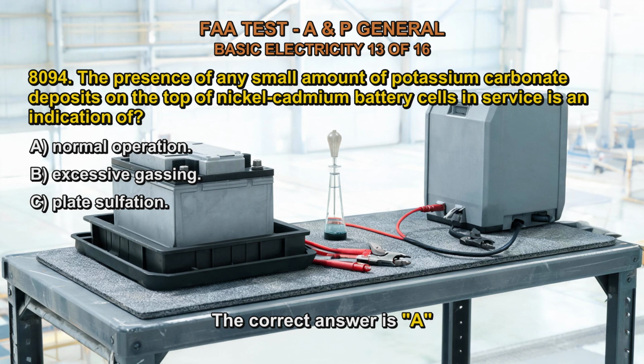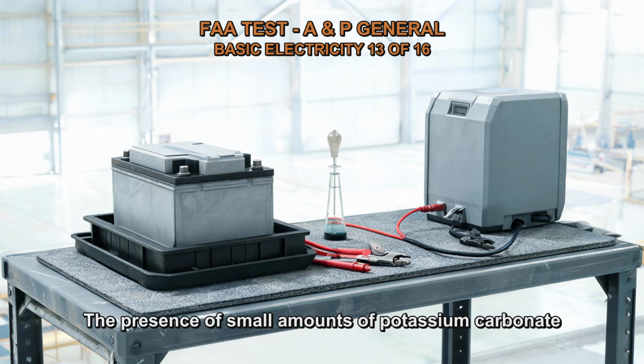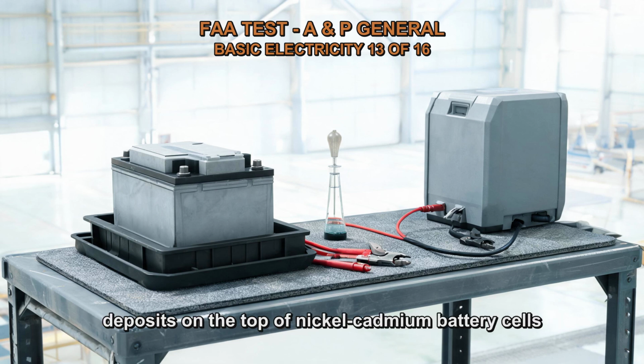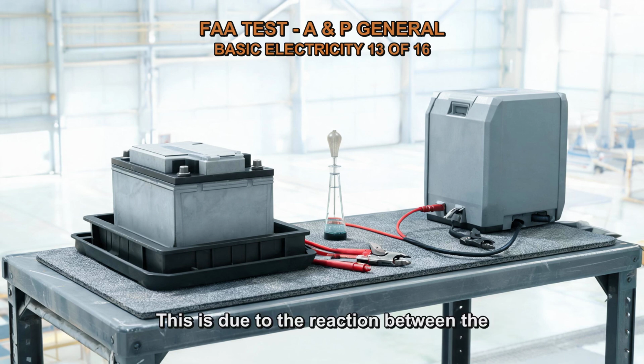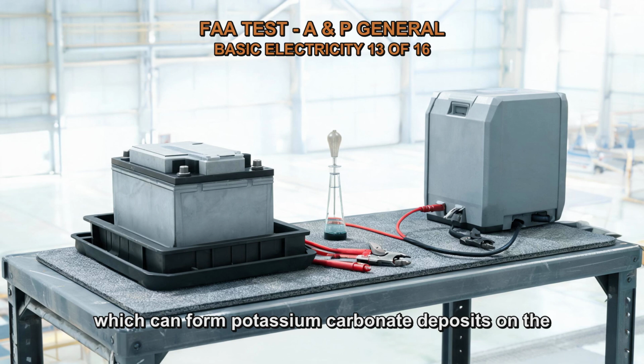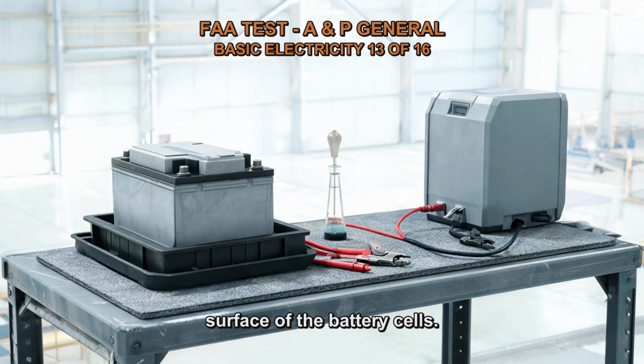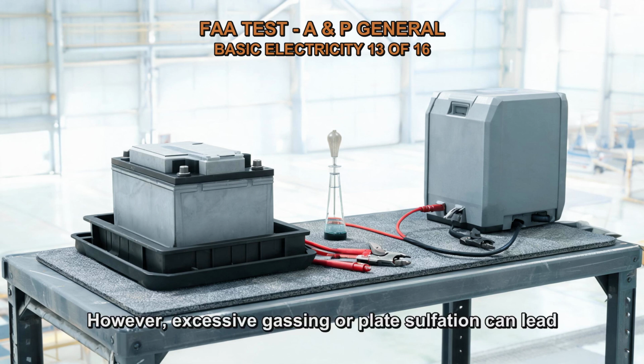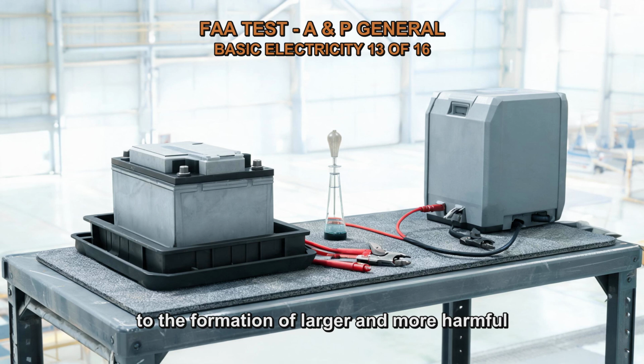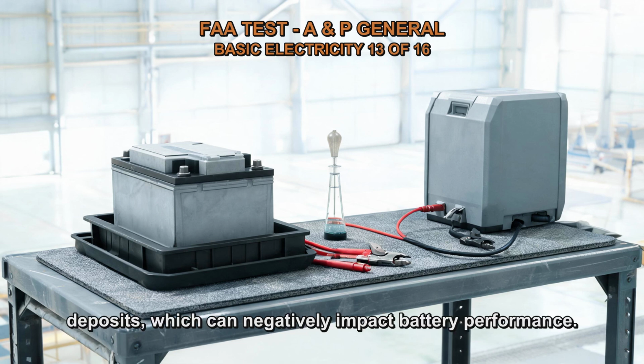The correct answer is A. The presence of small amounts of potassium carbonate deposits on the top of nickel-cadmium battery cells is a normal occurrence during battery operation. This is due to the reaction between the electrolyte and the vented gases from the cells, which can form potassium carbonate deposits on the surface of the battery cells. However, excessive gassing or plate sulfation can lead to the formation of larger and more harmful deposits, which can negatively impact battery performance.